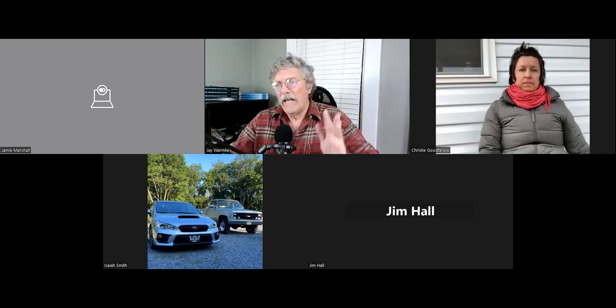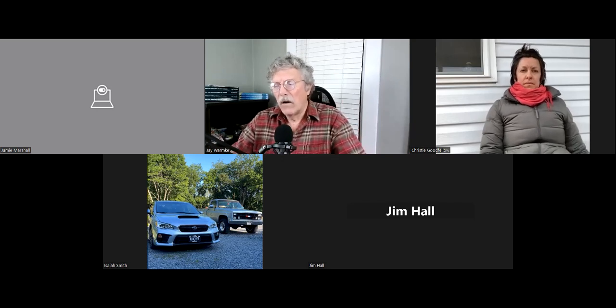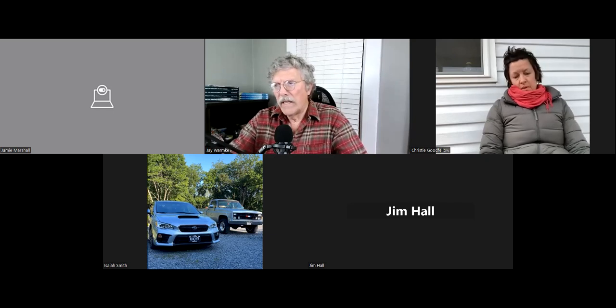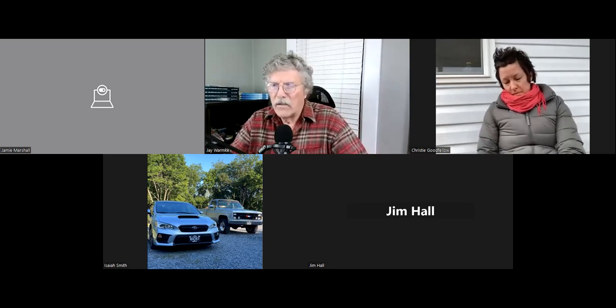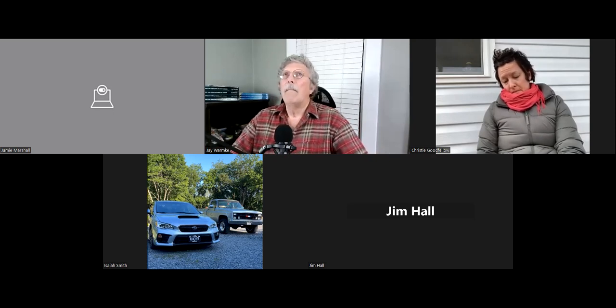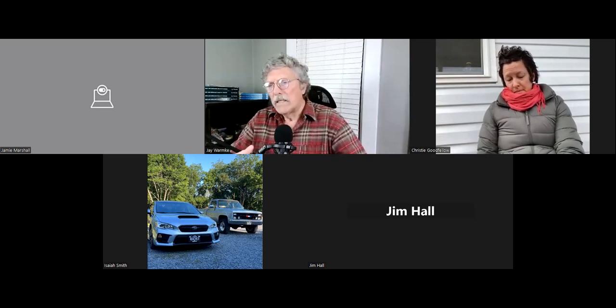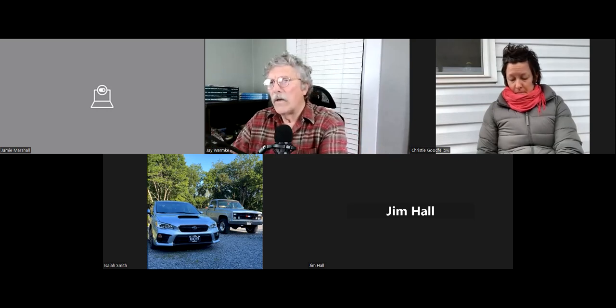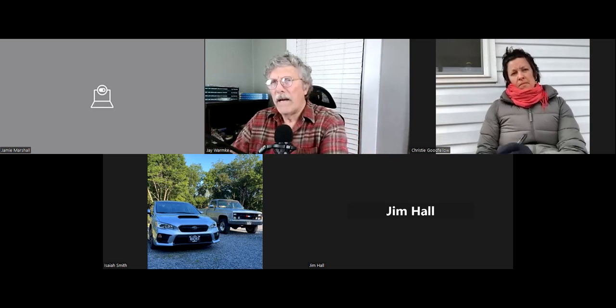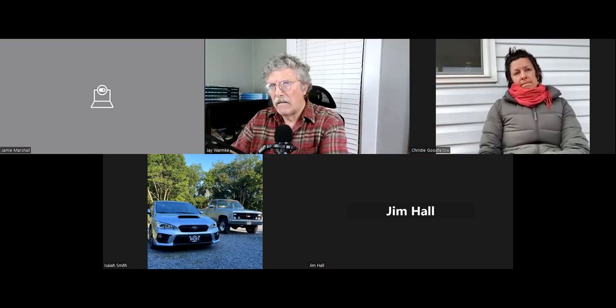So where are you east to west? We're always going to want to try and face it as close to south as possible. You don't want these things facing north, because that's just not where the sun is in the northern hemisphere. But going from east to west, if you're facing due east, you're going to lose about 20% of the amount of energy than if you're facing south.